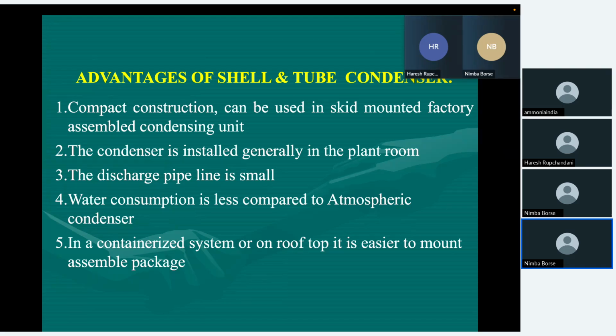The condenser is installed generally in the plant room. So the piping is very small. Compressor to condenser piping becomes very small. If you use an evaporative condenser, the piping could be pretty large. The water consumption is less compared to an atmospheric condenser. I'm not comparing with an evaporative condenser; in an evaporative condenser also water consumption is low. But compared to a general atmospheric condenser, which is an open condenser, the water consumption is less.